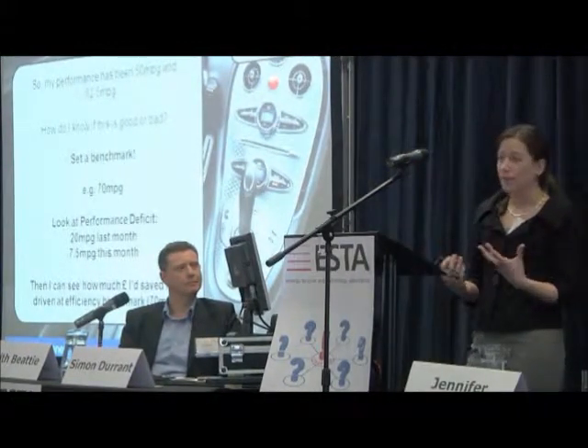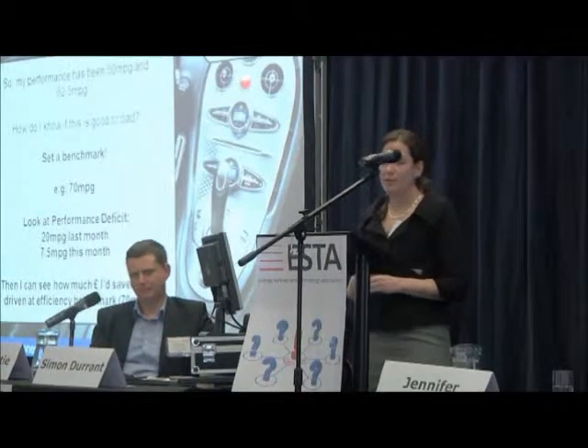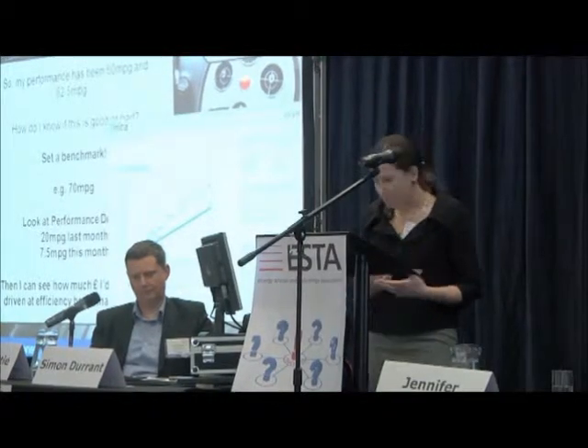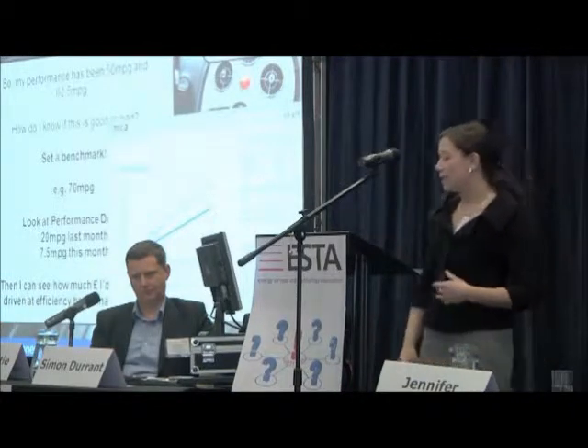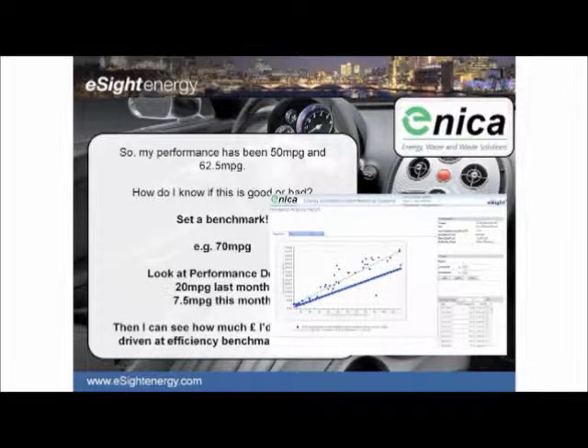But what might we do next? Say I can see that my efficiency has improved — how do I know if that's good or bad? This is where benchmarking comes in: either against your own sites or against government targets, you can look at what your performance deficit might be, or even whether you've been overperforming — which is a great thing to communicate to your organisation. An example of how Enica reviews this comes from a steel manufacturing site in Wales, where they've been comparing gas consumption against temperature. If the gas boilers are firing correctly, data points should all be nicely correlated along the green line of best fit. Enica set a target line slightly below that to bring everything down a little, helping organisations stay on track as things change over time.